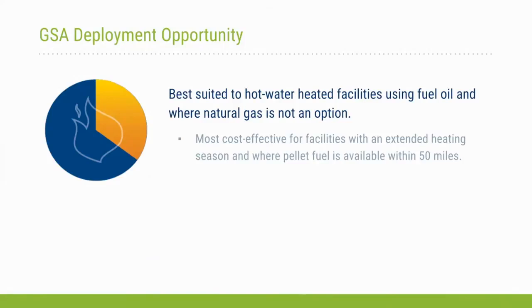Just to wrap up, these systems are suited for hot water facilities. Typically, if you're using a biomass fuel, you're probably displacing fuel oil. You don't want to look at projects where natural gas is an option, since natural gas prices are very low now and easy to put in place. So most of these facilities are going to be economical in colder climates and more remote areas—places like Alaska, or the rural Northeast and similar areas—where natural gas isn't available.